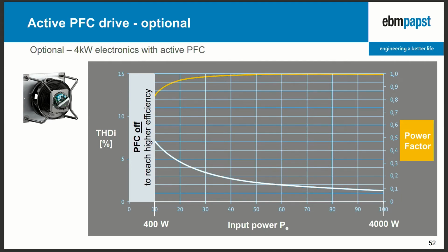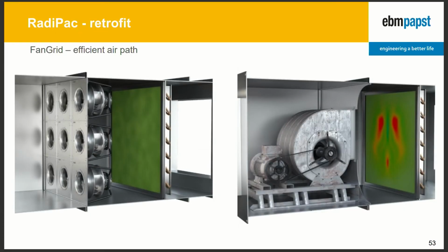As mentioned, this electronic can be fitted on all our motors, 4 kilowatt only at the moment, but this is quite helpful in applications where the requirement asks for that feature. Retrofit, fan grid, efficient air path. So it's the same that I mentioned before. This kind of plenum fan creates a pressure evenly distributed in the plenum. And when there's a heat exchanger, the airflow through this heat exchanger is evenly distributed, and so the efficiency of this heat exchanger or filter is optimized.